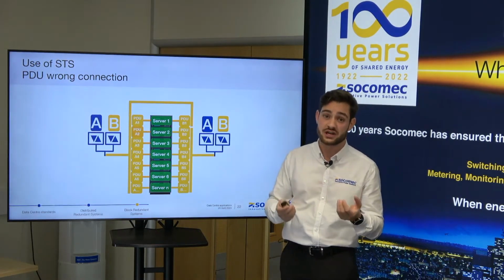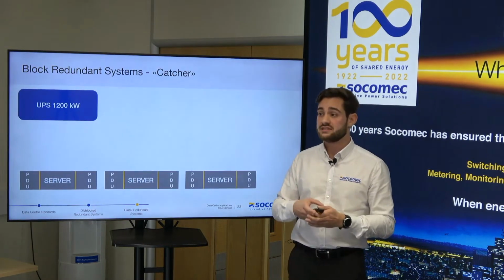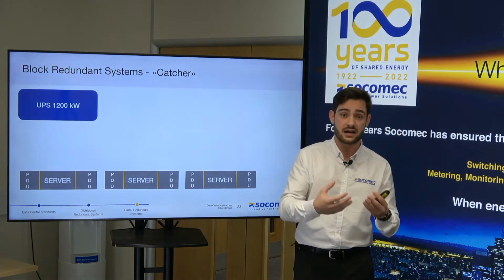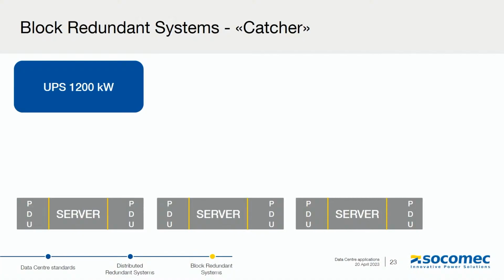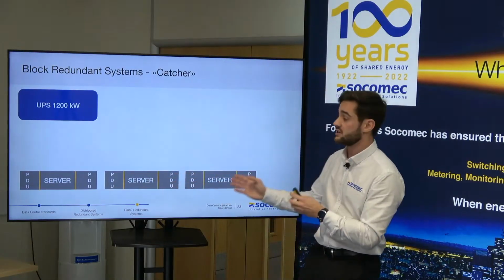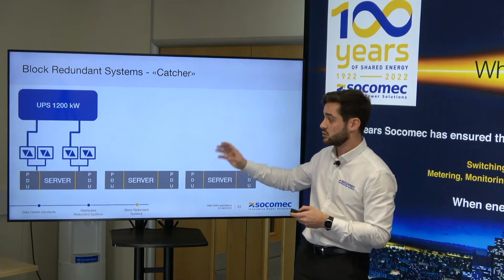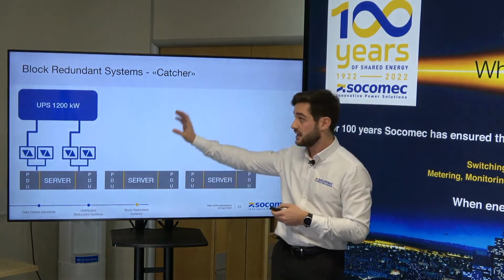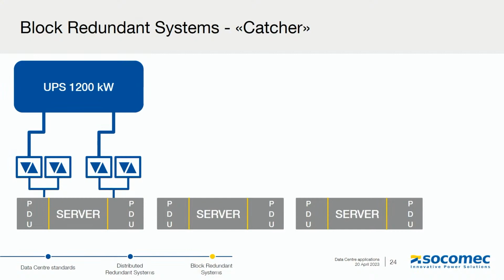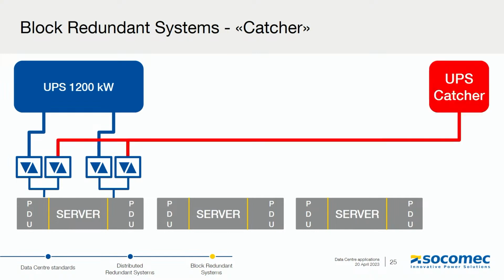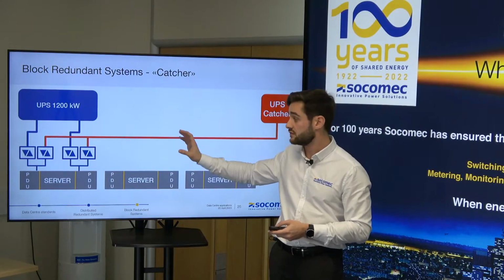So catcher is probably jargon that you've heard a lot. We see now a lot of drawings and customers mention catcher, but what does it really mean? Because it can be a little bit confusing. So we can actually put a word on that. Again, imagine you've got some dual corded servers fed via PDUs, 50% on each leg, and the UPS system. So we now include the STS system, and the UPS system is feeding all the primary sources for the STS, and then the STS is connected to the power supply. Then you incorporate a UPS catcher that is feeding the alternative source of each STS system.